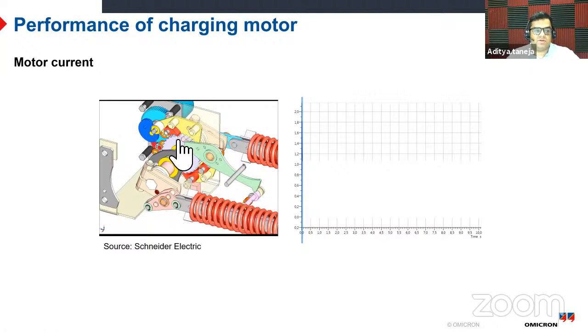So we check the current drawn by the motor to charge this whole mechanism, and the profile can be different. It's very vendor specific. There is no easy representation. Normally the vendor gives the normal charging current, inrush current, and charging time to help you do the analysis. But you can also look at the profile, which is good for comparison in case there are problems. So here I will again start a video where this will work. It will operate, and we will simultaneously see how the current profile looks for the motor.